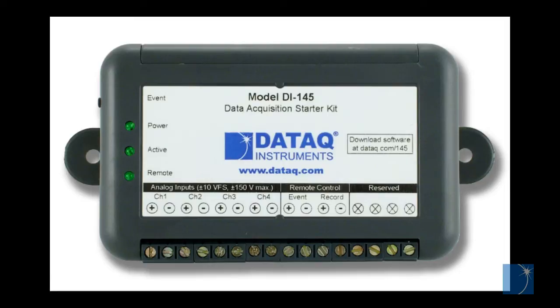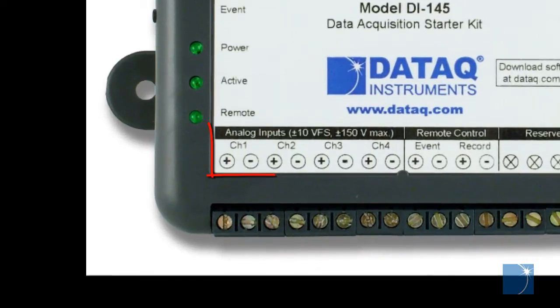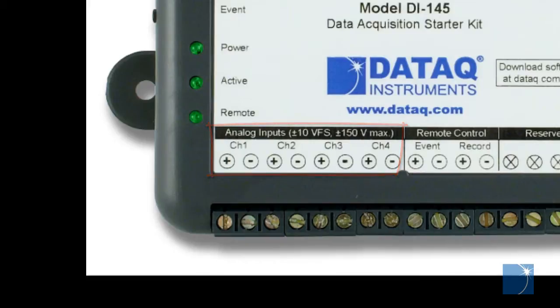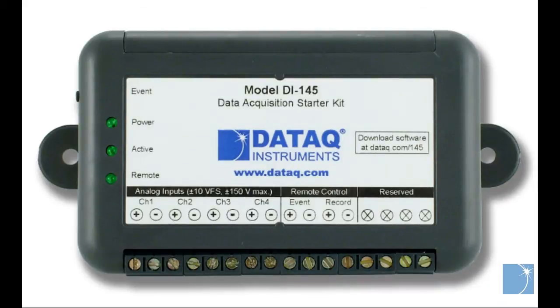The DI145 is a low-cost USB connected data acquisition instrument. The four fixed differential analog inputs have a plus or minus 10 volt full-scale measurement range with 10-bit resolution and over-voltage protection up to plus or minus 75 volts continuous or 150 volts for up to a minute.